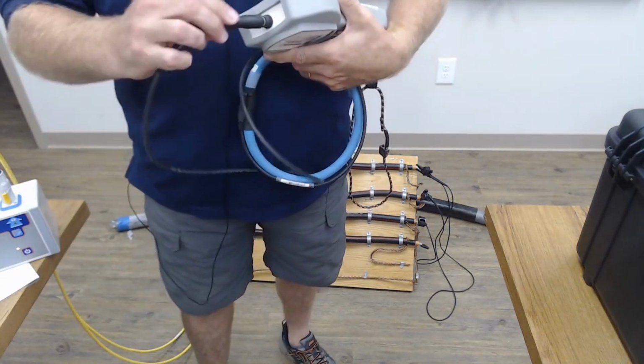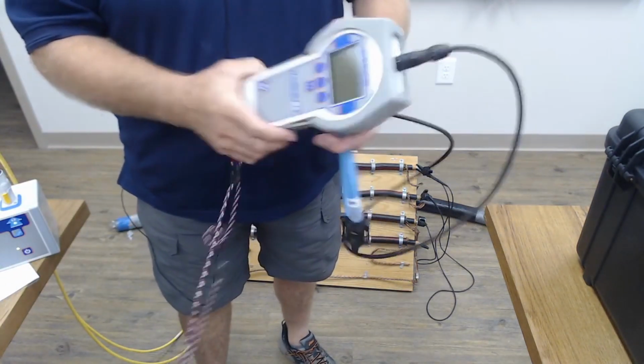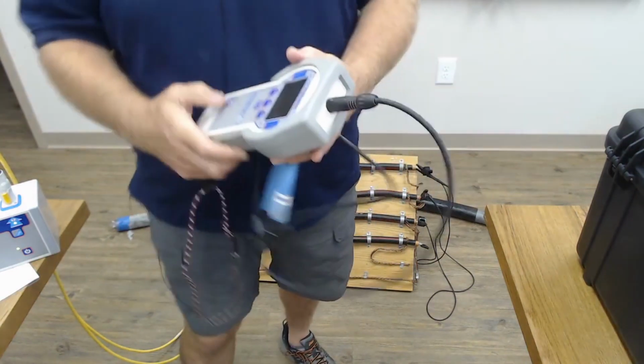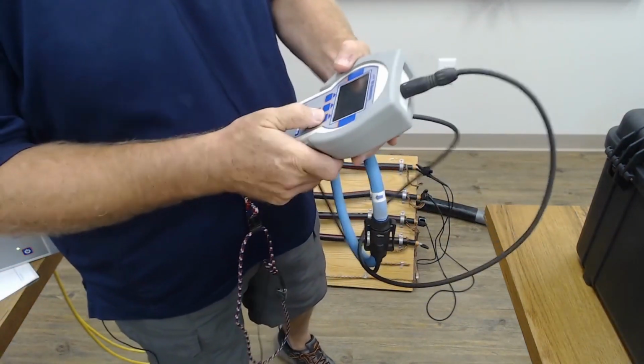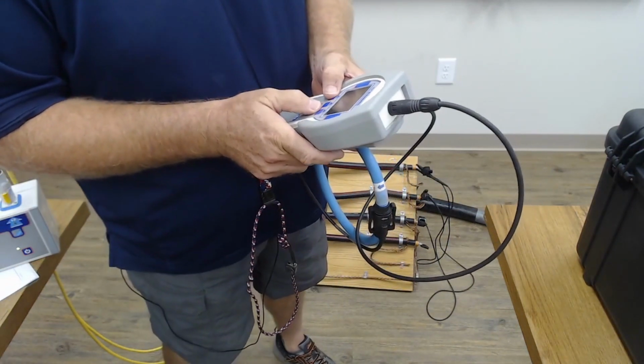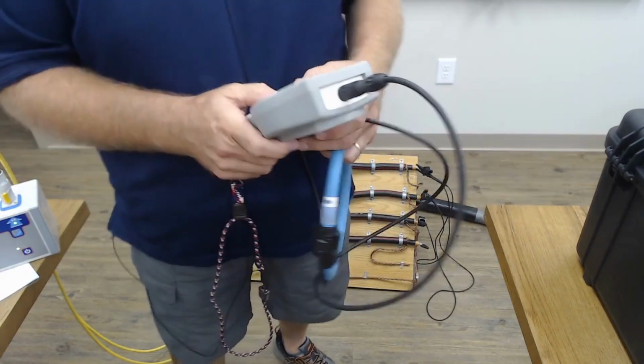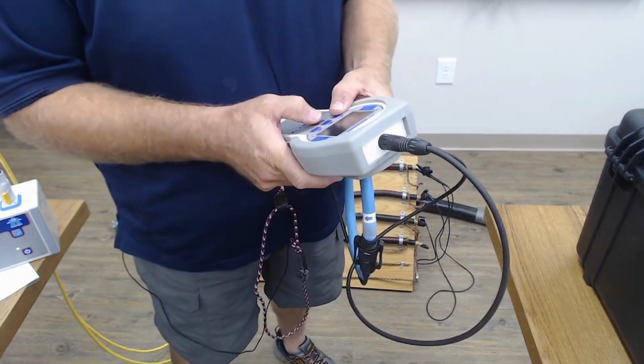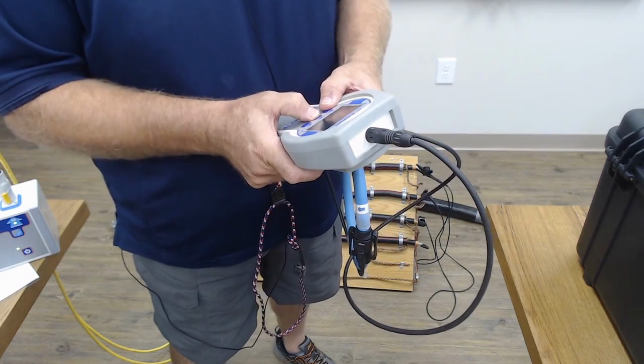Now we take our receiver. Because we have individual cables that we can get around, we're going to use our Rogowski coil, which is this guy over here. We're going to turn on the unit. And we're going to do what we call uncalibrated mode first. Uncalibrated mode is when you do not have to verify the amount of current at your source. You are only picking up the unique signal coming down L1 and L2, with the two signals returning on L3. This mode is quicker, but it does require more understanding.